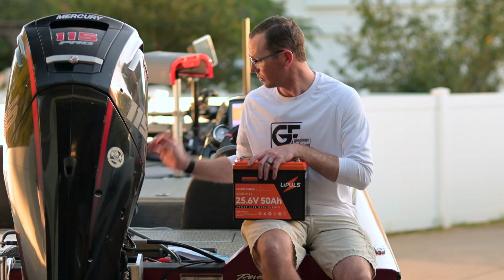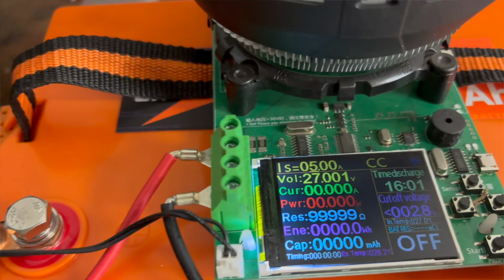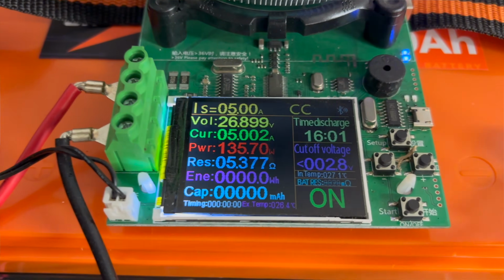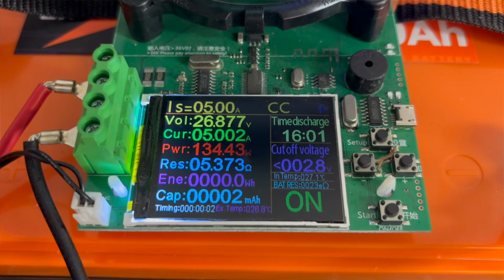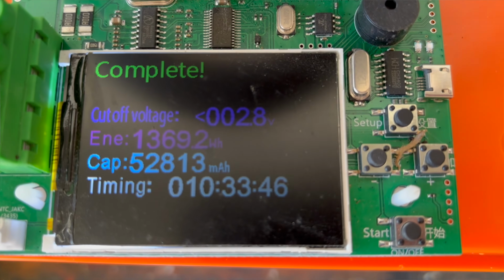We fully charged it with our LiPULS 24 volt charger, which we'll talk about in a second, and then we did a 5 amp draw on it at 24 volts, running it all the way down. It tested at just under 53 amp hours of usable capacity, which is nice. It's rated at 50, you're getting 53.